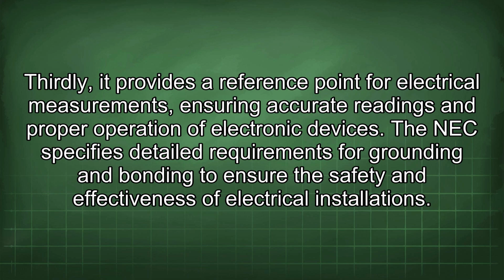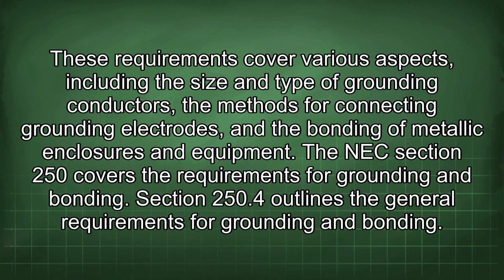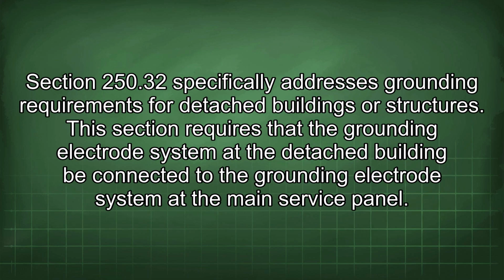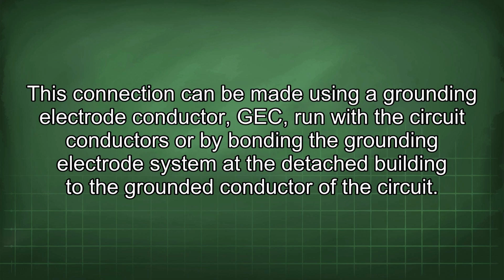The NEC specifies detailed requirements for grounding and bonding to ensure the safety and effectiveness of electrical installations. These requirements cover various aspects, including the size and type of grounding conductors, the methods for connecting grounding electrodes, and the bonding of metallic enclosures and equipment. The NEC Section 250 covers the requirements for grounding and bonding. Section 250.4 outlines the general requirements for grounding and bonding. Section 250.32 specifically addresses grounding requirements for detached buildings or structures. This section requires that the grounding electrode system at the detached building be connected to the grounding electrode system at the main service panel. This connection can be made using a grounding electrode conductor (GEC) run with the circuit conductors or by bonding the grounding electrode system at the detached building to the grounded conductor of the circuit.